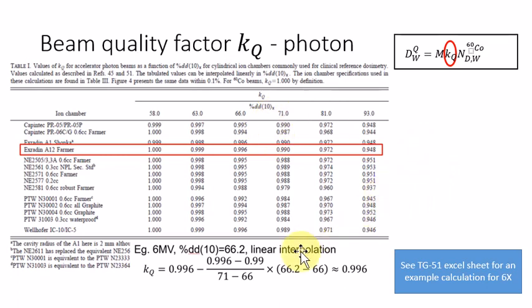For example, if we use the farmer chamber and our PDD at 10 equals 66.2, we use the 66 and the 71 value to obtain this KQ value for 66.2 by this linear interpolation equation. This is just an example of if we want to use the table to get the KQ for photon.